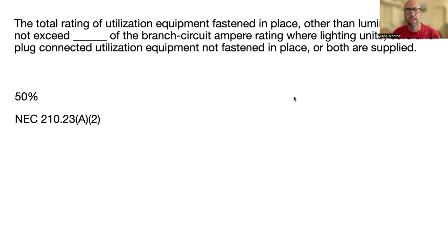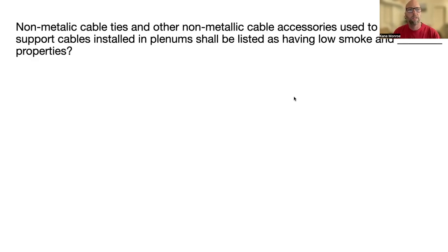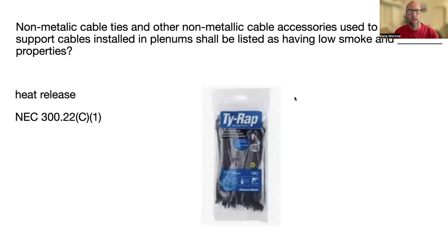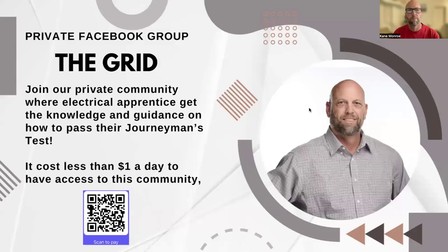Non-metallic cable ties and other non-metallic cable accessories used to secure and support cables installed in plenum shall be listed as having low smoke and low heat release properties. That's NEC 300.22(C)(1). This is referring to your basic tie wraps — that's all.